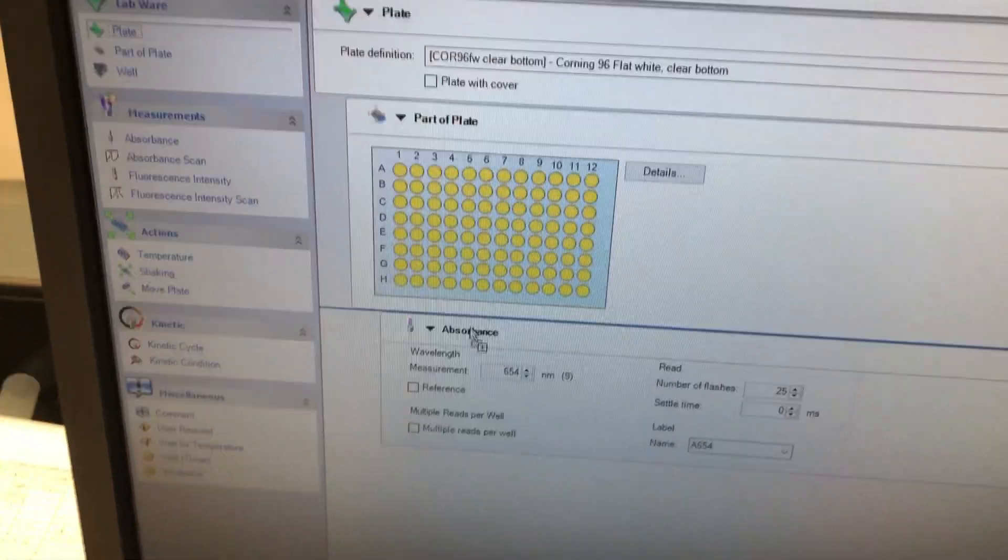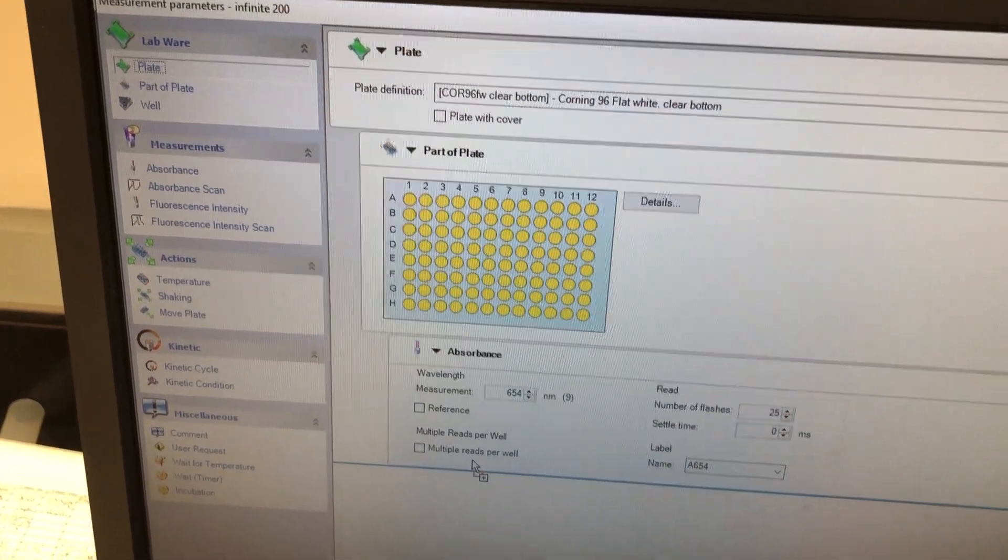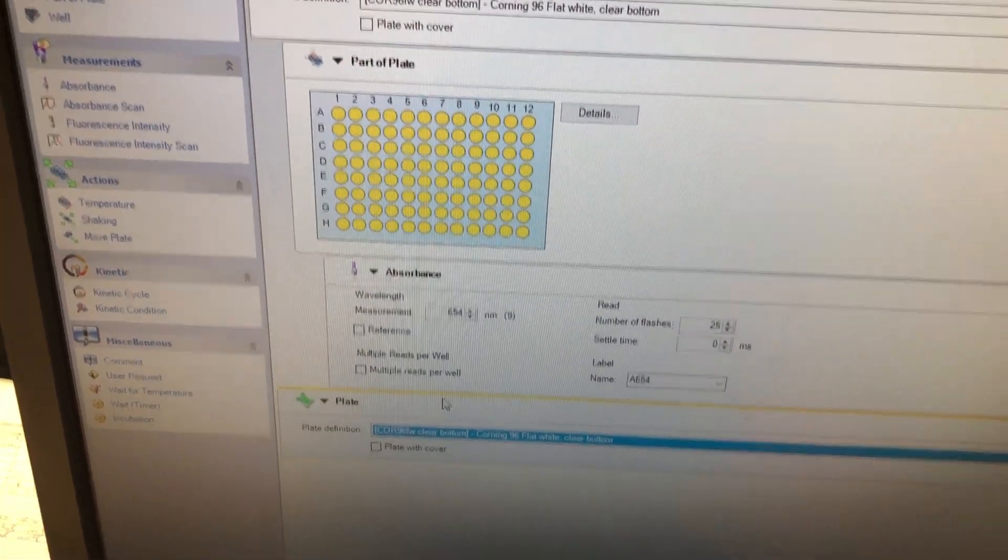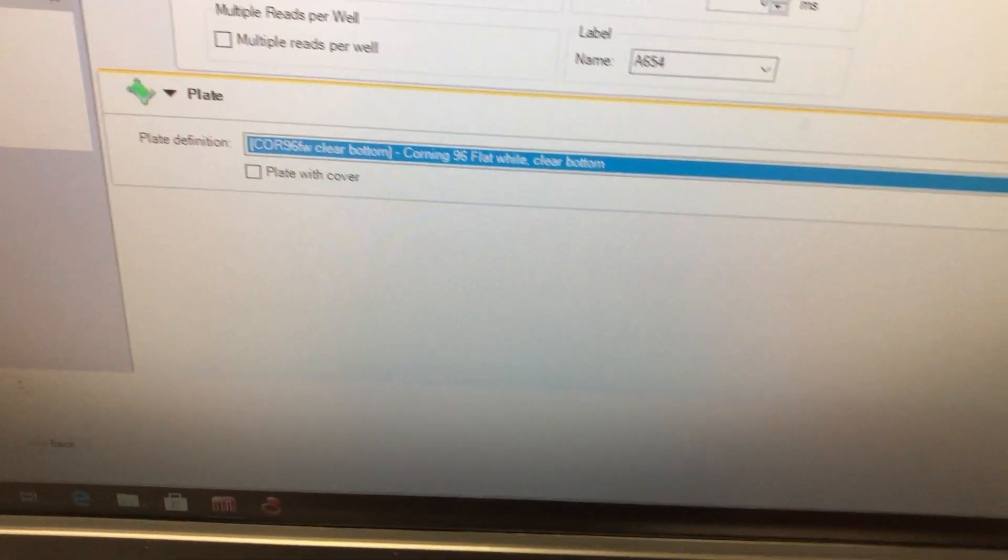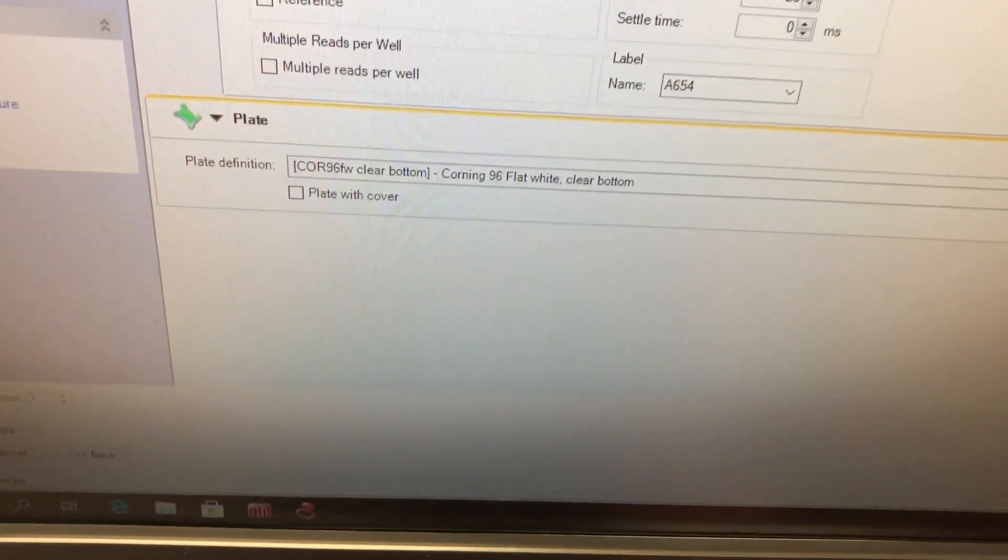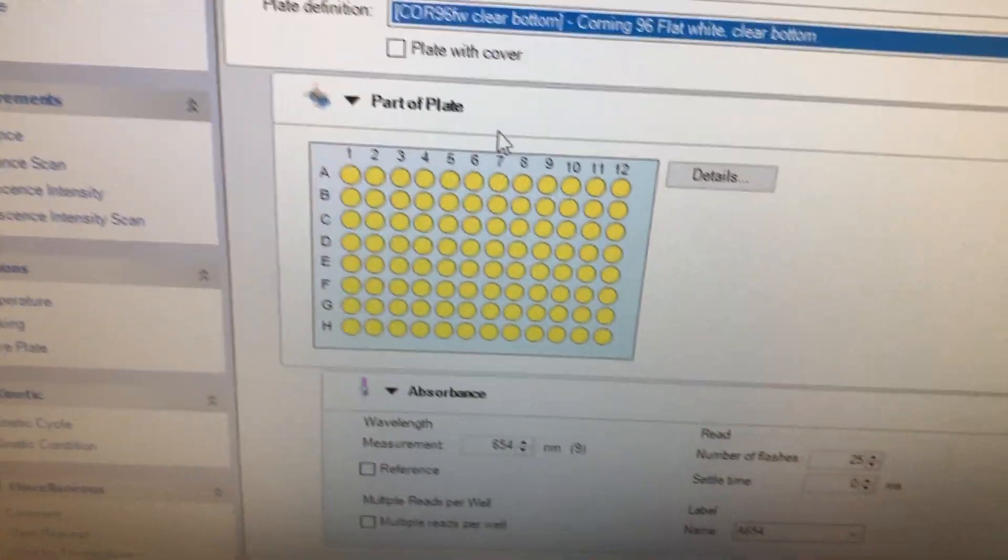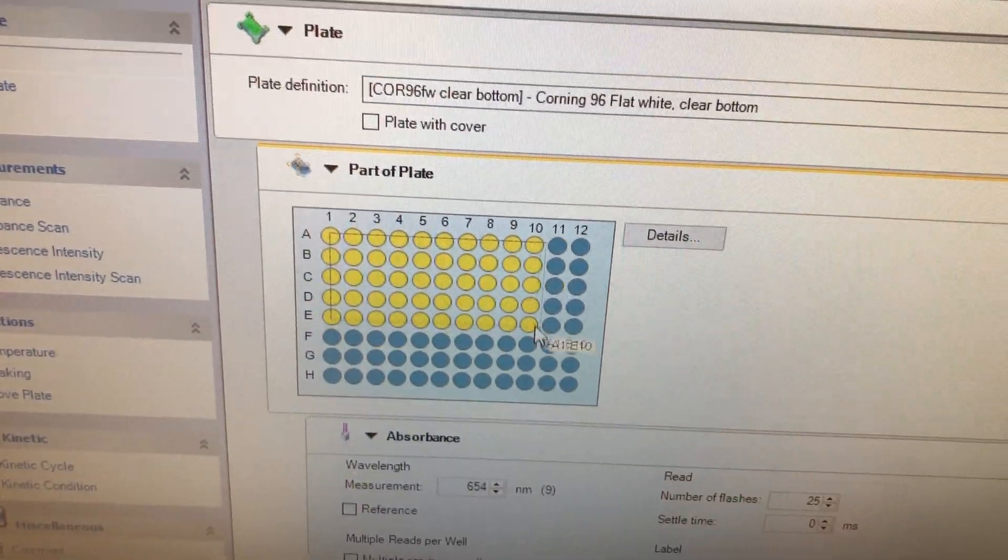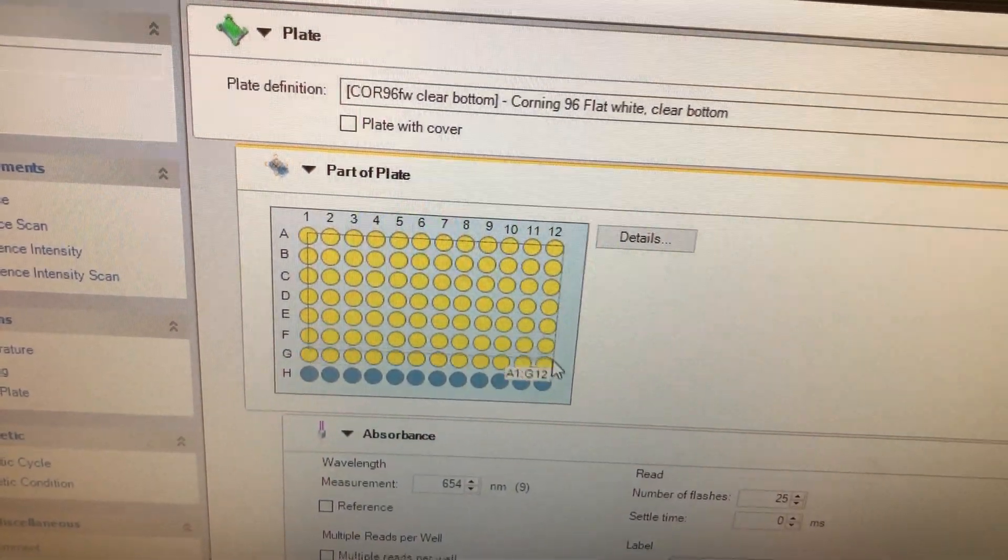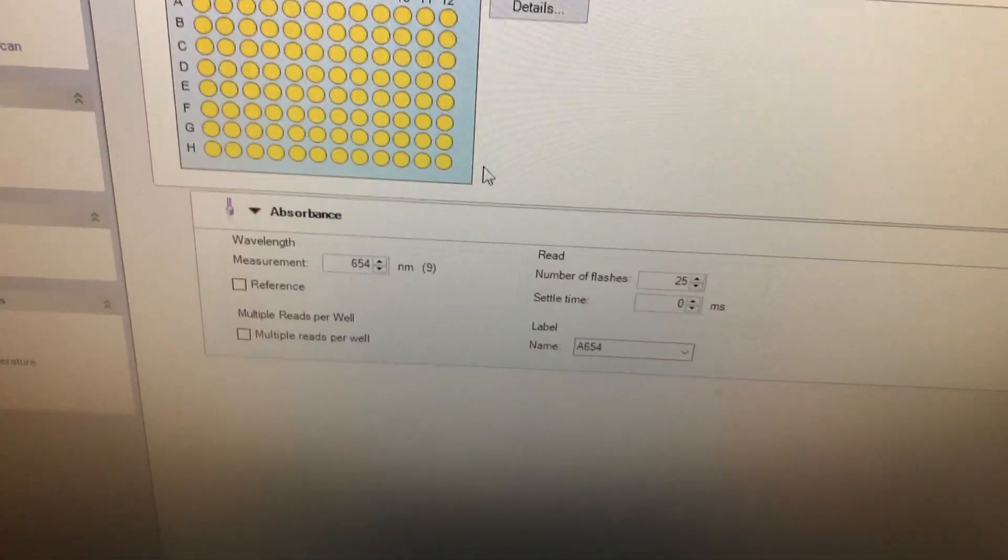You can just literally grab these little options over here. Like where do you want to measure? I want to measure the plate. Drop it there. Select what type of plate. We always use these clear bottom Corning 96-well plates. I'm going to right click on that and then press delete because we've already got one kind of dragged over here. And in this case we've actually got a part of plate dragged over here. When you drag over the part of plate, you're able to select from the mouse which wells do you want to measure. In this case, even though we're using part of plate, we'll go ahead and measure the whole plate.